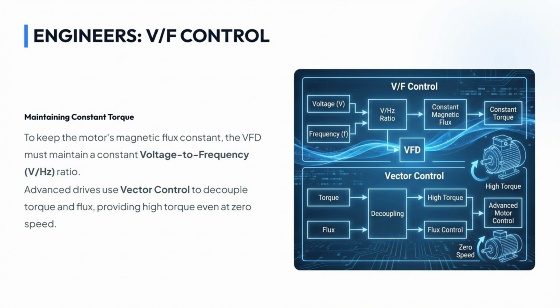For engineers, V/F control maintains constant torque by keeping a constant voltage-to-frequency ratio. Advanced drives use vector control to decouple torque and flux, providing high torque even at zero speed.